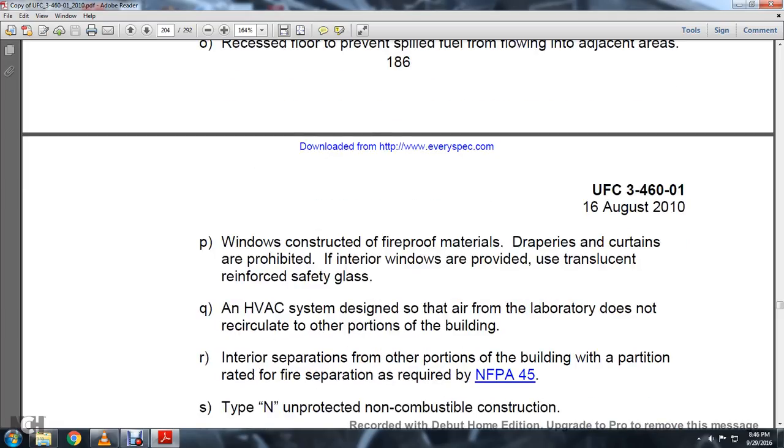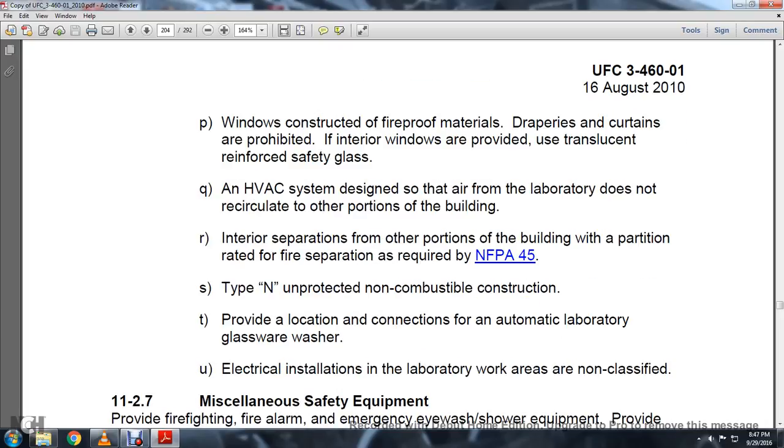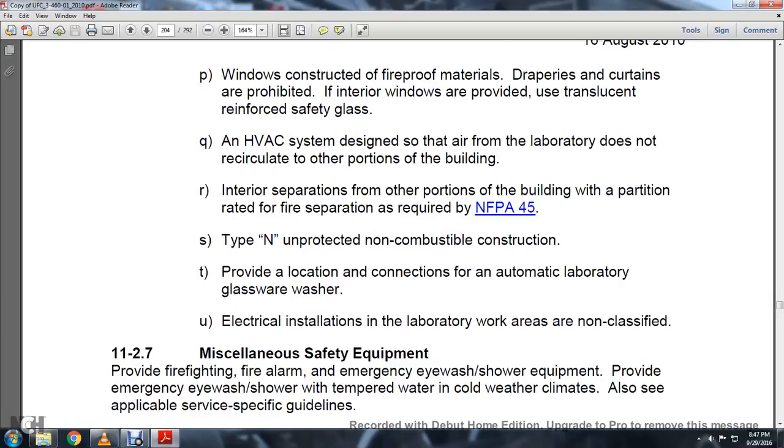Windows constructed of fireproof materials. Draperies and curtains are prohibited. If interior windows are provided, use translucent reinforced safety glass. The HVAC system is designed so that air from the laboratory does not recirculate to other portions of the building. Interior separations are the appropriate portions of the building with the partition, rated with fire separation, required per NFPA 45, provided with Type N non-combustible construction. Provide location, construction, and connection for the automatic laboratory glassware washer. Electrical installation laboratory work areas are not classified.